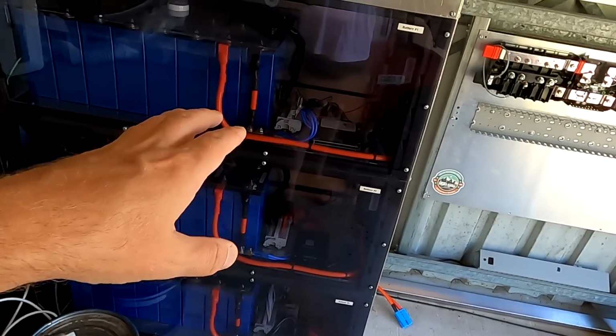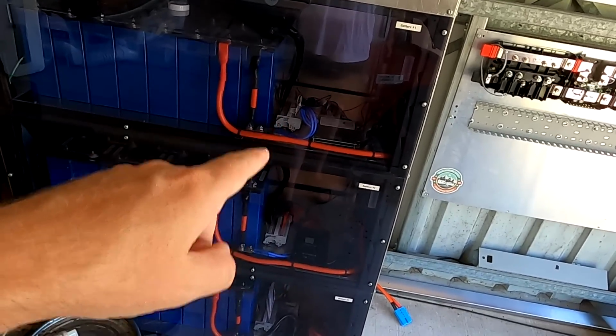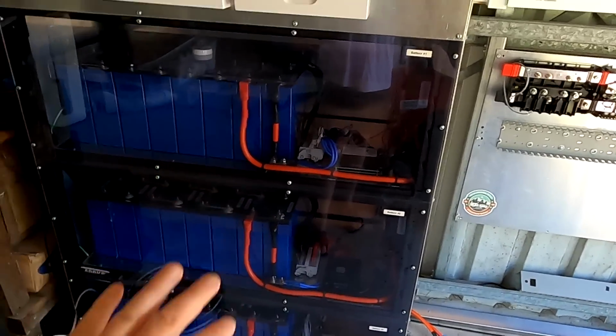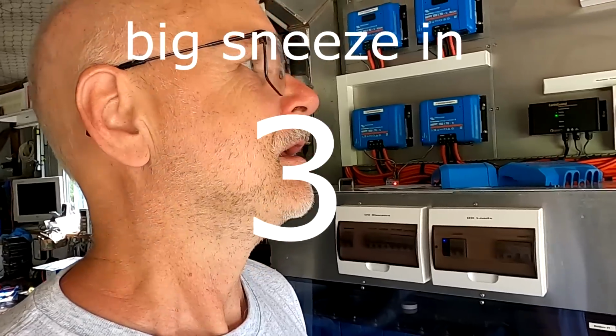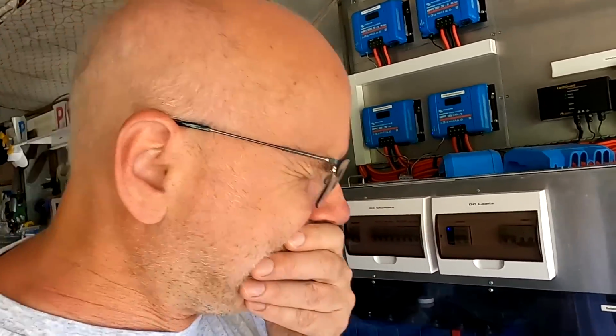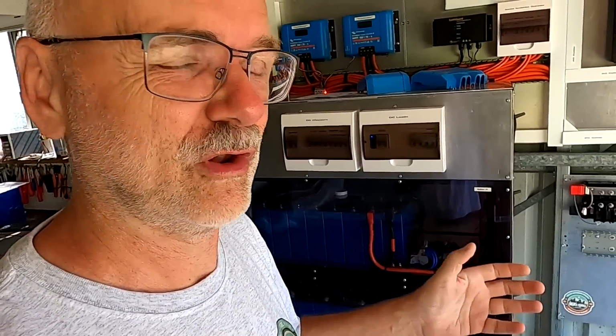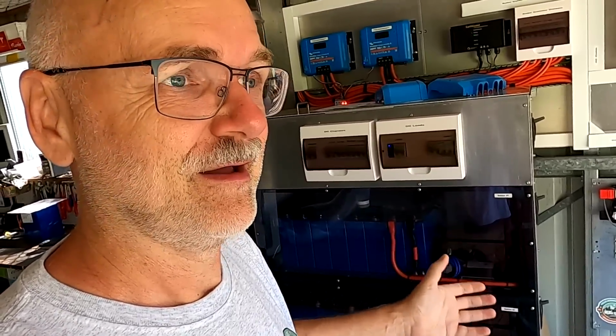As you know, we have seen around 250 to 260 amps going into these three battery banks here. If one of the battery banks were to shut down because of a cell overvoltage protection, a BMS fault, or the circuit breaker tripping, and you lose one battery, this 250 amps will then split into the remaining battery banks and cause issues there. We'd have a fairly quick shutdown of the whole system.